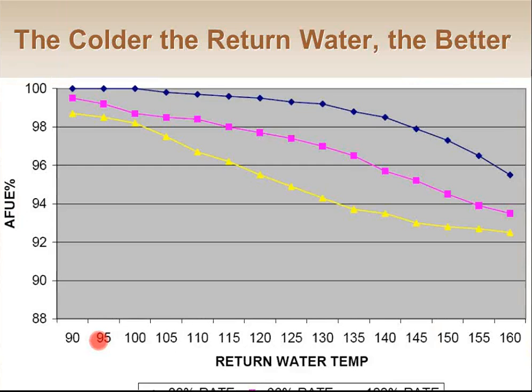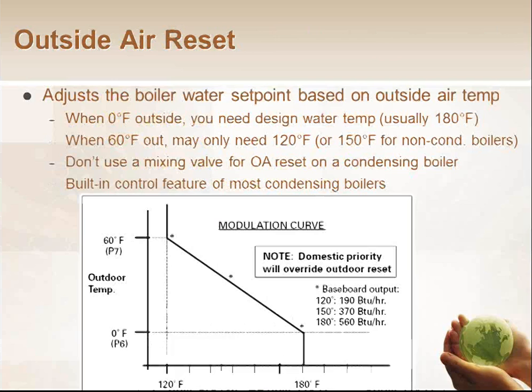For other systems where I don't have snow melt type water and cold radiant floors, how do I get these water temperatures lower? Well, the thing I can realize is that I don't need 180-degree supply water every single day of the year, right? If it's a 0-degree day out, fine. I need 180-degree supply water because that was my design. But at any other point in time, I don't need 180, right? If it's 60 degrees out, I can get away with a lot cooler water.